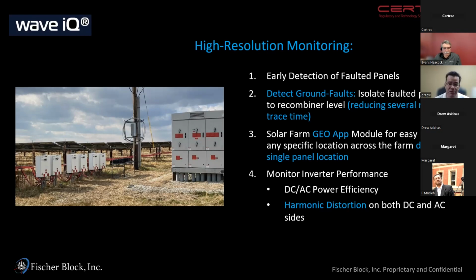And without any type of high resolution monitoring, it can be very difficult to get to the source of a ground fault. Some of these technicians have to walk miles physically looking for and doing portable tests to find a ground fault. And so being able to put current sensors down in the combiner lines and the recombiners, we typically can get within a few hundred feet of a ground fault and save a couple, 3 days of diagnostic time if there is a problem, and even then provide some predictive analytics as well if things are getting worse.